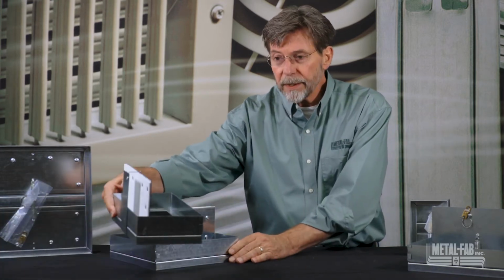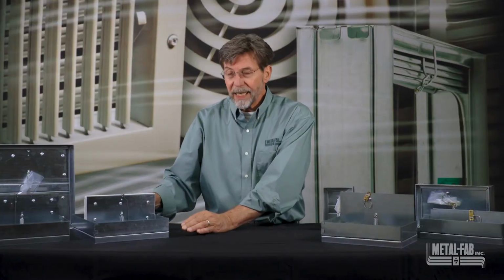This is a DynaGuard dynamic ceiling radiation damper. We've got them available in a dual blade butterfly type design, and we've also got the single blade that you can see here. The assembly that these are approved for use with is the M557. So if you see an M557 requirement, if you're looking at the International Mechanical Code, you see a requirement for dynamic ceiling radiation dampers. These are the products you can use.